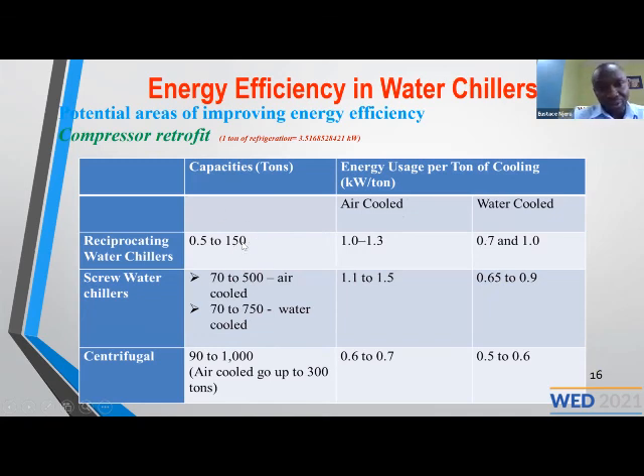But if you have a cooling load of more than 150, don't use a reciprocating compressor. You should go up to the screw compressor, for example. If you have more than 500 or 750, go to the centrifugal compressor. I think it's clear.